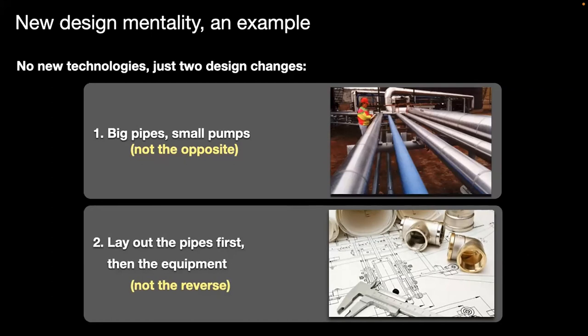Traditionally you put the tanks, boilers, whatever, in some convenient traditional arbitrary place, and then you call in the pipe fitter to connect point A to point B. But by then A and B are far apart, other stuff got in between, they're at the wrong height, they face the wrong way. And by the time the pipe snakes across the space, all dressed in neat right angles like they teach us in trade school, it has about 3 to 6 times the friction it would have had with a straight shot. The pipe fitters like this because you pay them by the hour, they mark up the extra pipes and fittings, and they're not paying for your bigger pumping system or your bigger electric bill forever after.